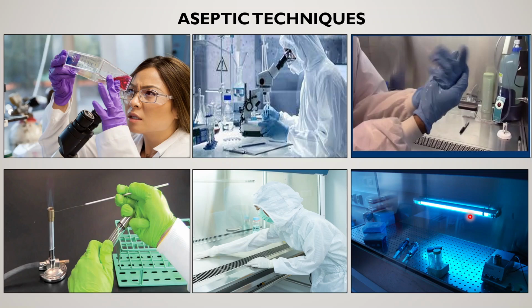But there is a limitation to using the autoclave: you can only use heat-stable equipment, as the autoclave subjects it to a temperature of about 121 degrees centigrade and a pressure of 15 pounds for 30 minutes. So this is how it is usually done.